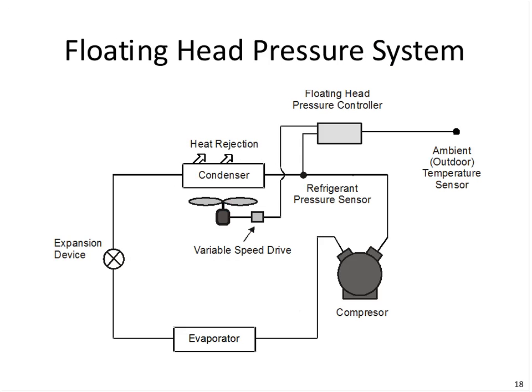Floating head pressure control diagram here, saying that we measure the ambient conditions, measure the refrigerant pressure, and then adjust the speed of this fan to attain a set point. Notice here the variable speed drive or variable frequency drive or permanent magnet DC motor, whatever technique we use here to adjust the speed of this fan to get to a set point that's attainable, and of course the ambient is a moving target throughout the day and throughout the year.